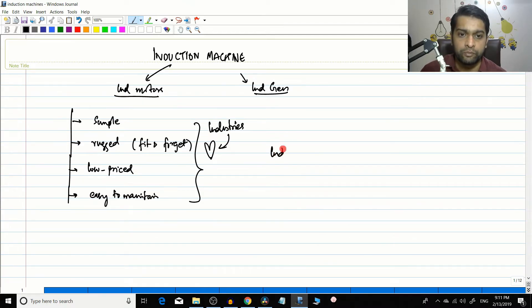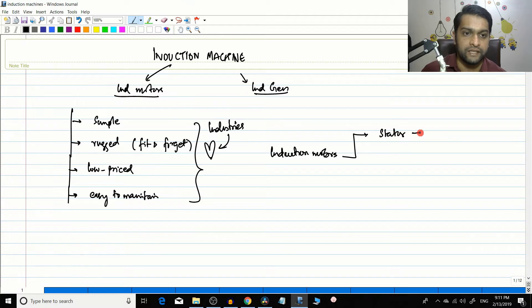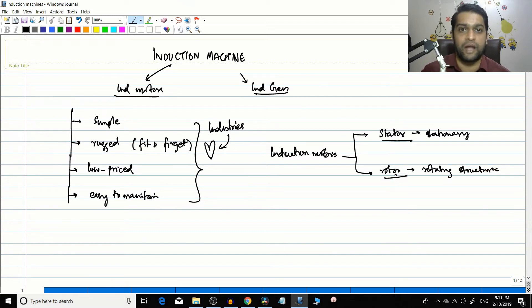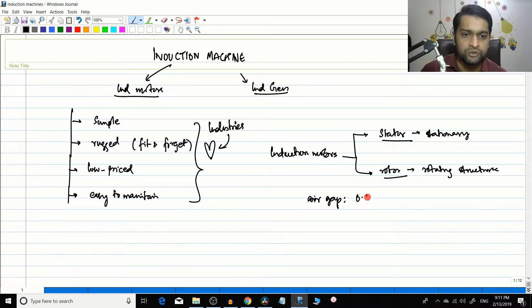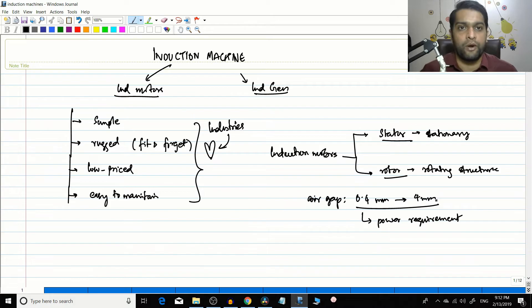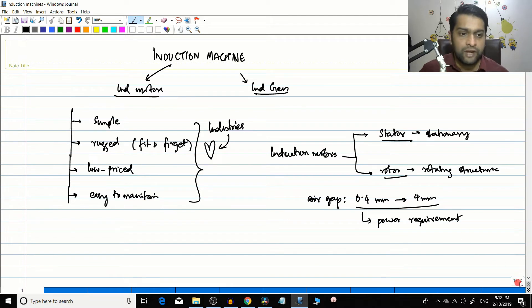Just like any motor, the induction motor has two principal components. One is the stator — the stationary structure — and the other is the rotor — the rotating structure. To rotate properly, there must be a gap between stator and rotor. This air gap in an induction motor is very small, typically from 0.4 mm to 4 mm, chosen based on the power requirements of the application.